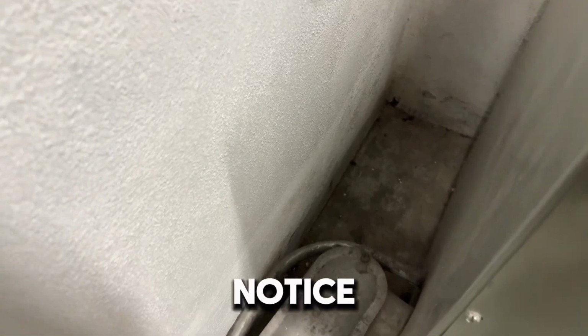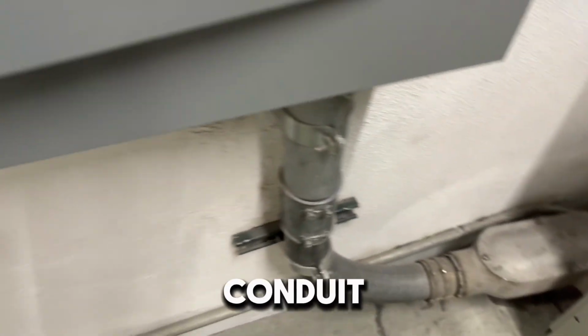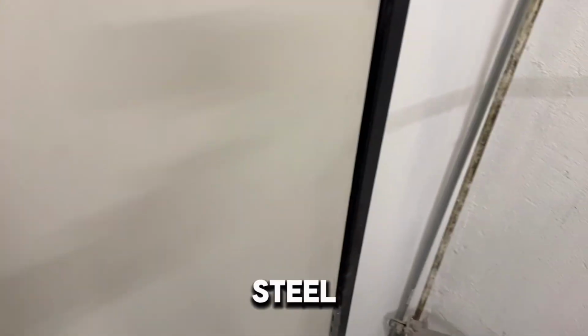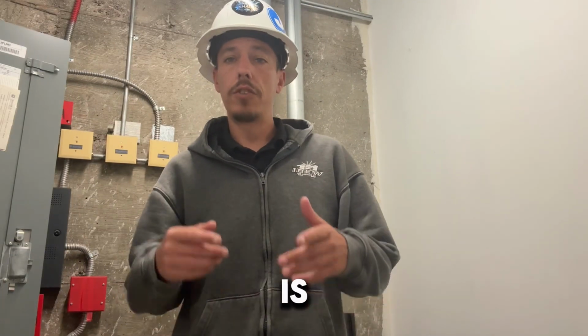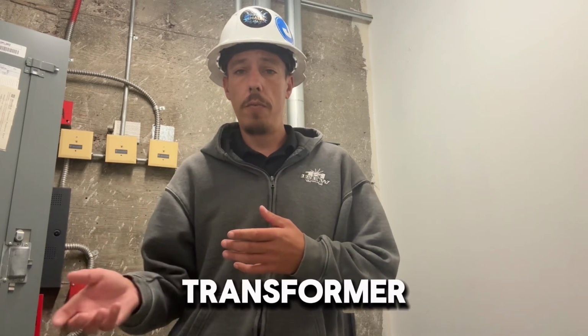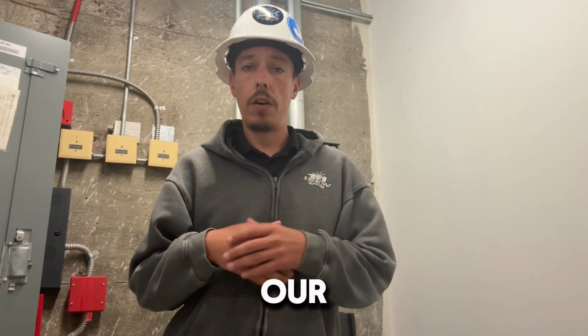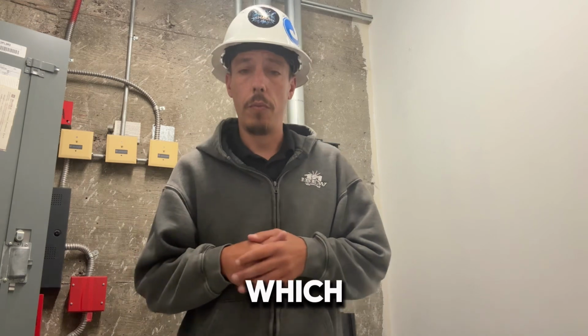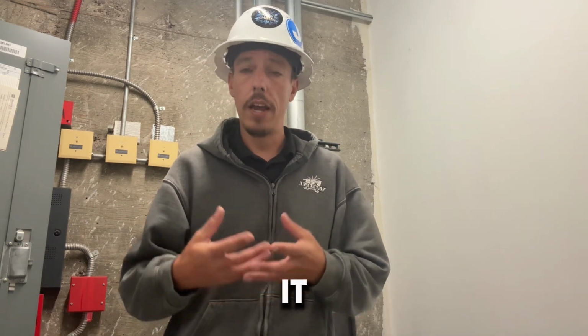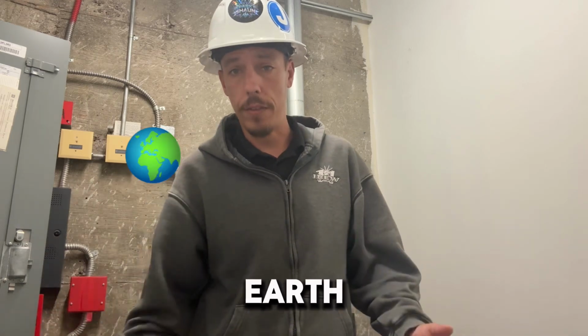And then last thing to notice, there's another 3/4 inch conduit that comes up and around, and it goes to our building steel. So our building steel is going down through each floor and tapping off each transformer, and then eventually going into our concrete encased electrode, which is our foundation that has rebar in it. And from there, it actually goes to direct earth.